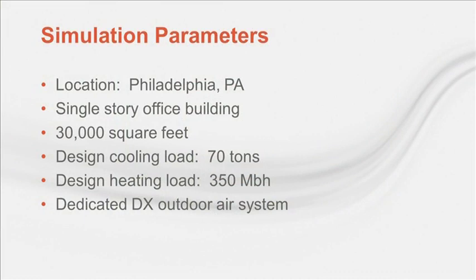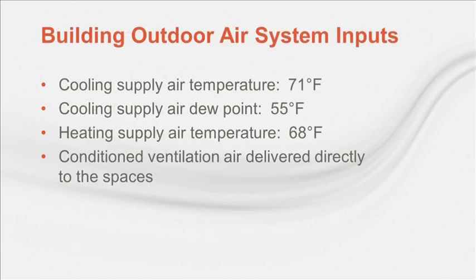The building is located in Philadelphia, Pennsylvania, and has a design cooling load of about 70 tons and a design heating load of about 350 MBH. The building has been designed to comply with ASHRAE Standard 90.1/2007. Of course, a portion of the load is from ventilation, and with VRF systems, a separate outdoor air system is often used for this ventilation load. In our simulation, we'll use a separate DX dedicated outdoor air system, which is fairly common. In the simulation, the outdoor air is being delivered directly to the spaces at or near room neutral conditions. It is being dehumidified to a dew point of 55 degrees and reheated to 71 degrees Fahrenheit.